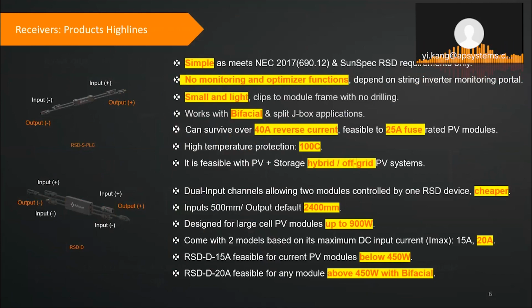When we designed the new device, we already considered certain situations it would have to survive from reverse current. So we referenced the string inverter standard requirement, and right now we can survive 40 amp reverse current for 2 hours, same as the string inverter requirement. We are also feasible for the 25 amp fuse rated PV panel right now. Internally, this device has a sensor and a high temperature protection function up to 100 degrees C. When it reaches that, it immediately shuts down the whole device.